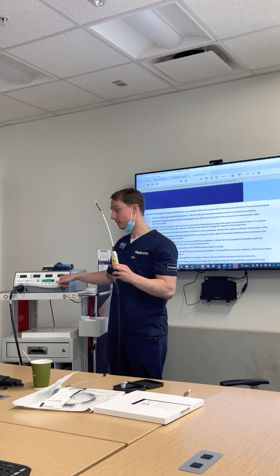What we'll do, go back to the air leak. So if we've checked all the different positions here, we've connected this, and I'd say 98% of the time that works. If for whatever reason this connection is tight, this connection is tight, and the air filter is tight, that's typically a faulty balloon in the catheter. Again, this happens very, very rarely, but I want you to feel comfortable with it if we do run into it. If these connections are all good, let's grab this catheter, disconnect it, and we have to pull it out of the patient again.